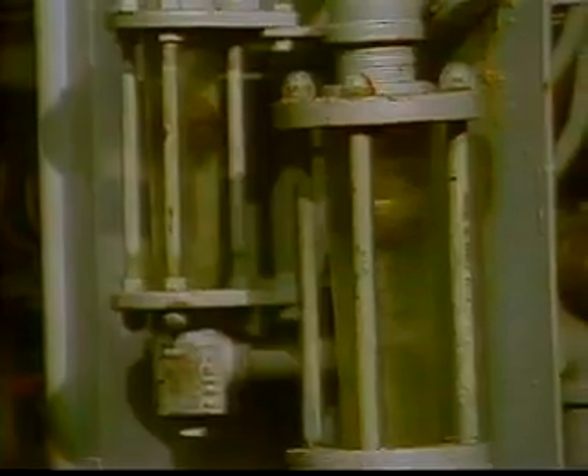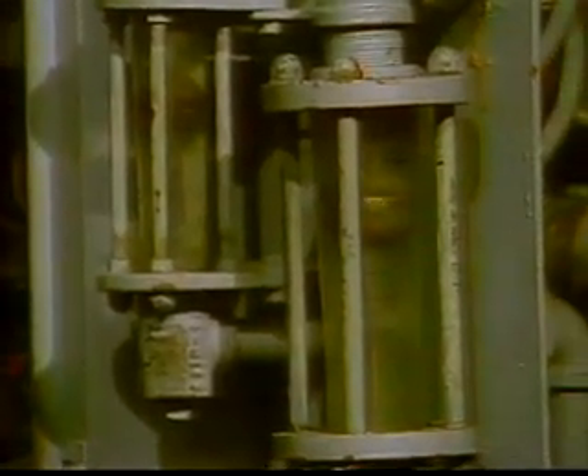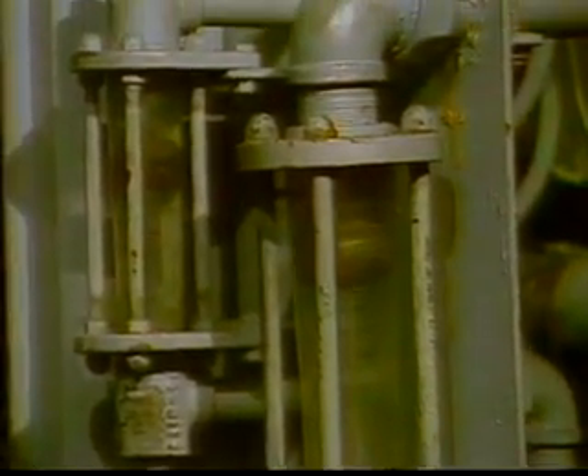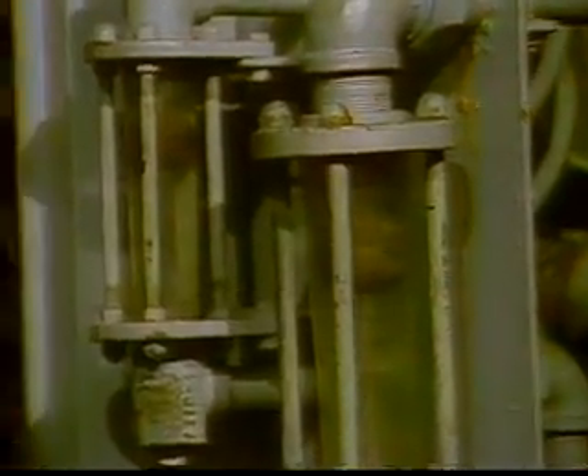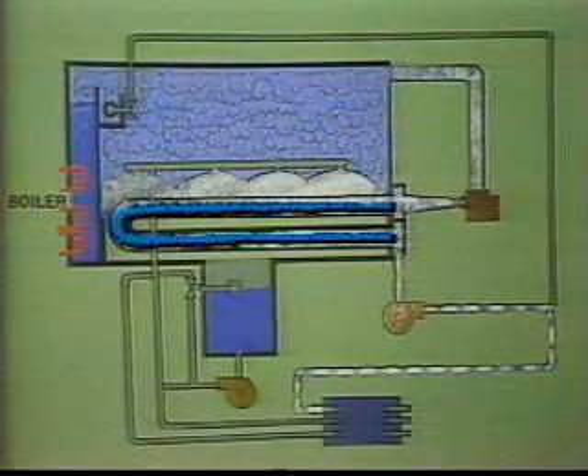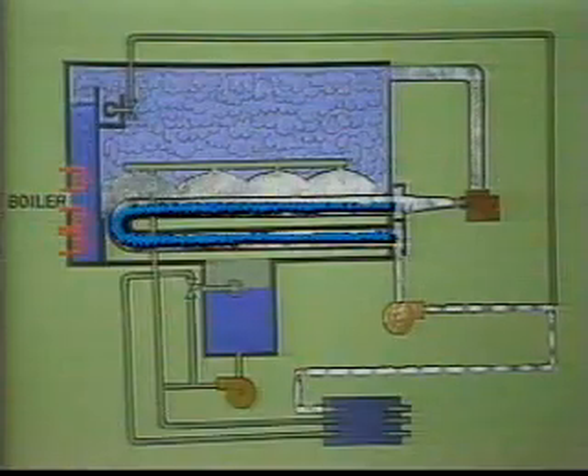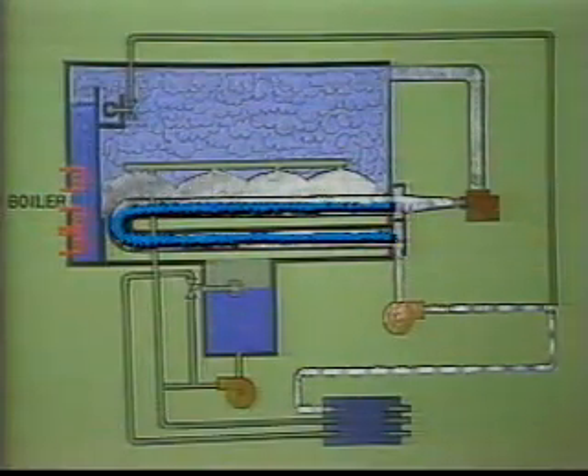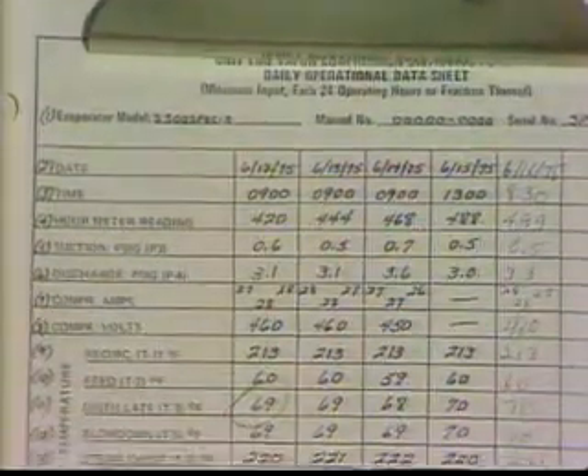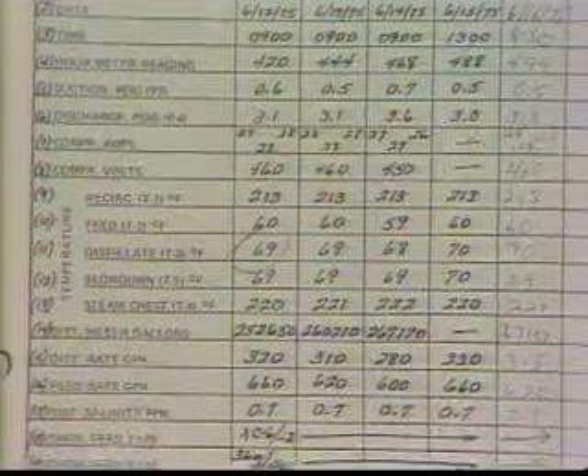Feed water rate has to be kept at twice the distillate capacity to prevent excessive concentrations of calcium sulfate scale from developing in the evaporator tubes. If these concentrations get too high, calcium and magnesium sulfate will form on the heating tube bundles, causing a need for AC8 treatment. Again, these records are important. Don't slough them off, because this is how you determine your problems before they shut your unit down.